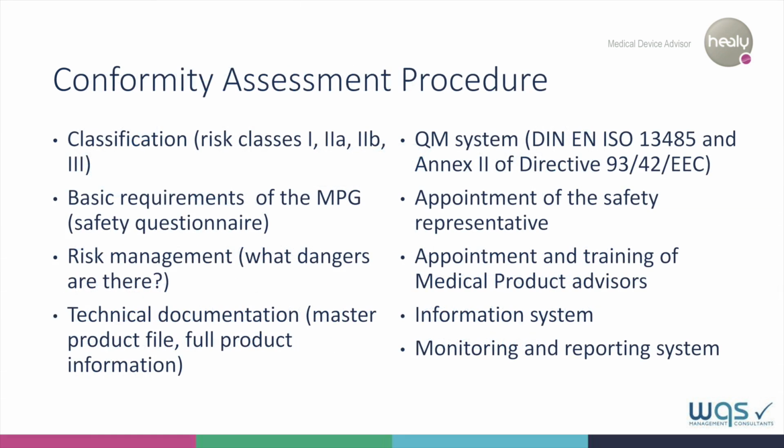Let's now move on to the so-called conformity assessment procedure. In order to carry the CE mark, manufacturers and their products must meet a number of strict requirements. These requirements include classification into one of the risk classes we just discussed, as well as compliance with all requirements of the Medical Devices Act. Proof of a risk management policy and detailed technical documentation of the product must be present.